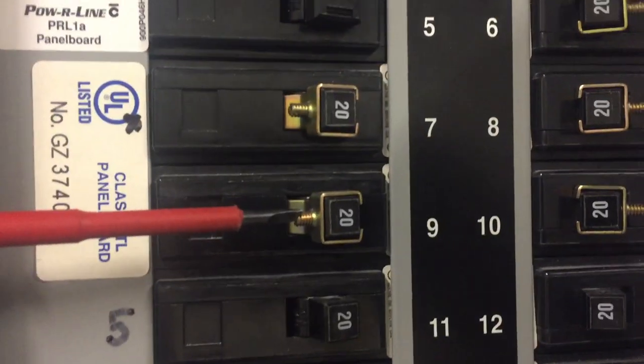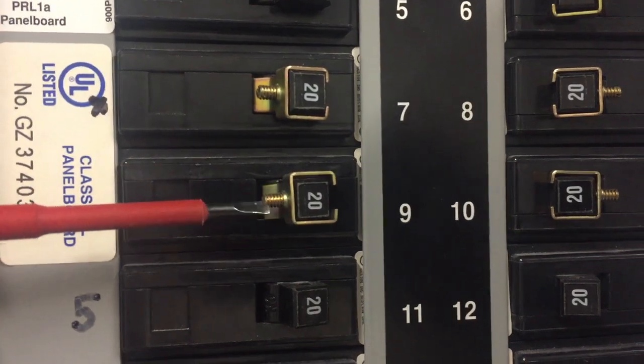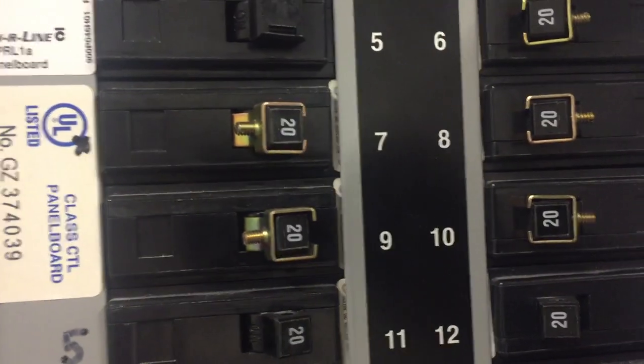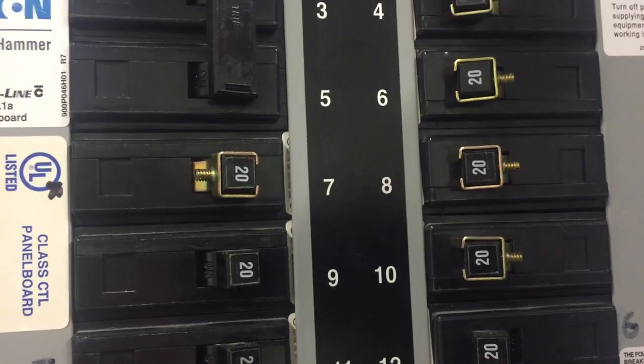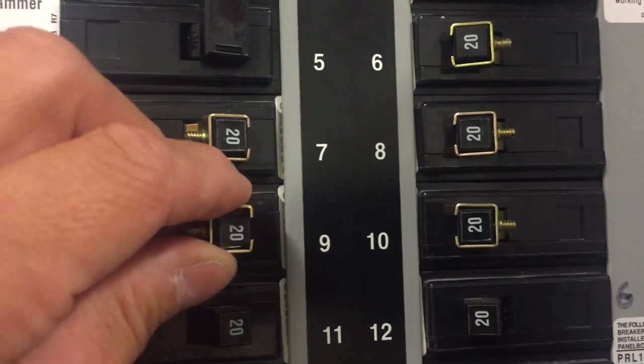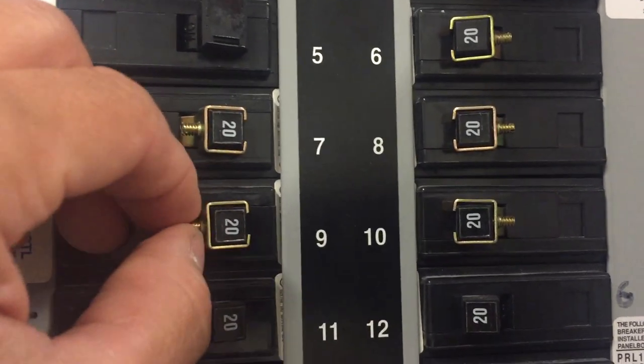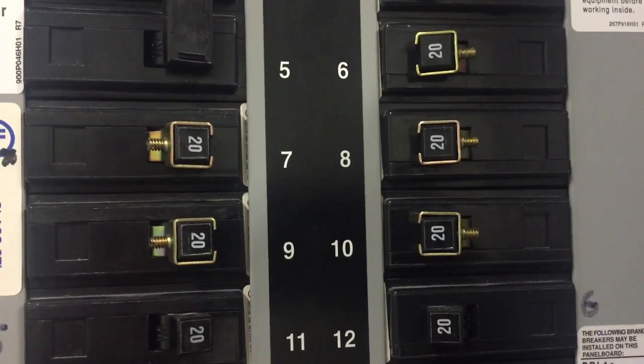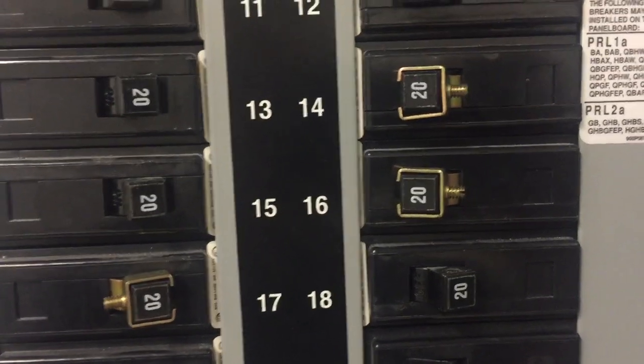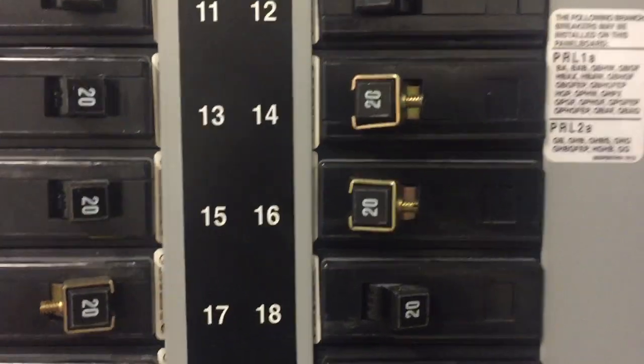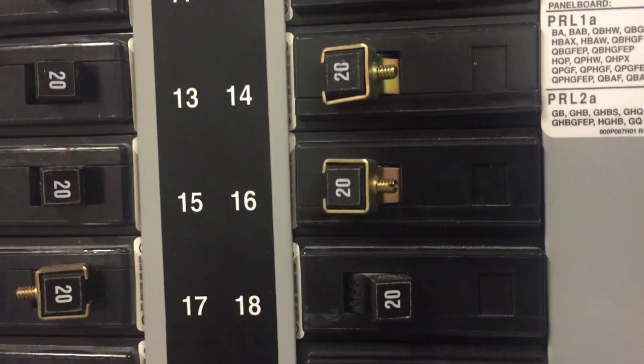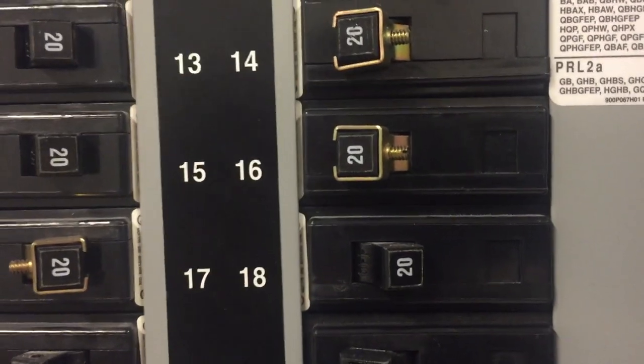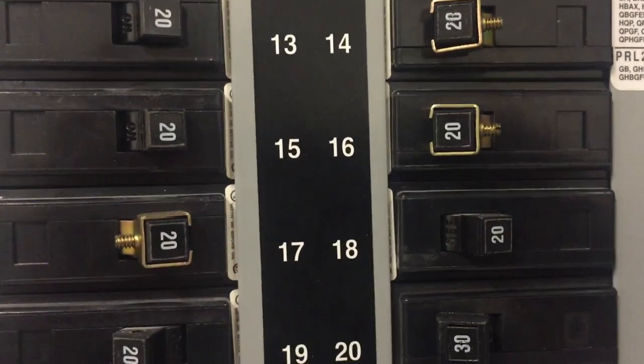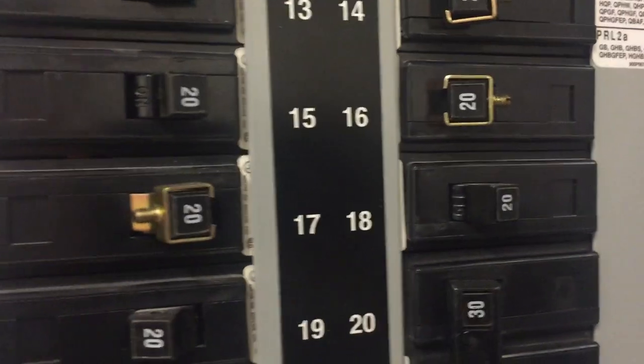Checking out these circuit breaker locks. See that? You need a screwdriver to install or remove these, which means since a tool is needed, they do not meet the Article 100 definition of readily accessible. So we end up having a violation because 240.24A requires circuit breakers to be readily accessible.